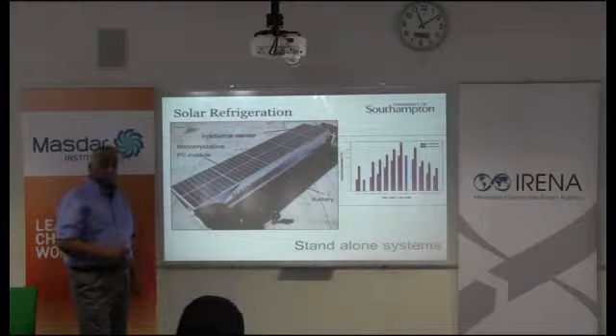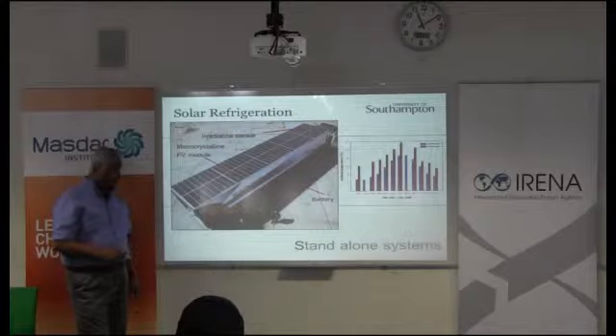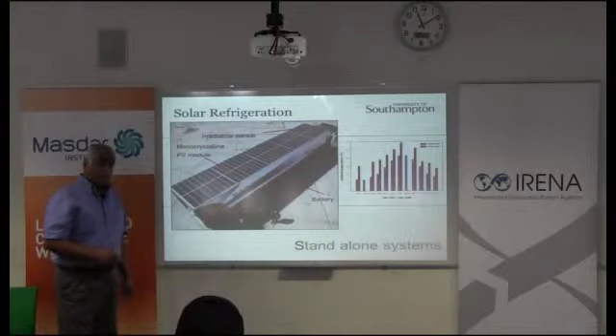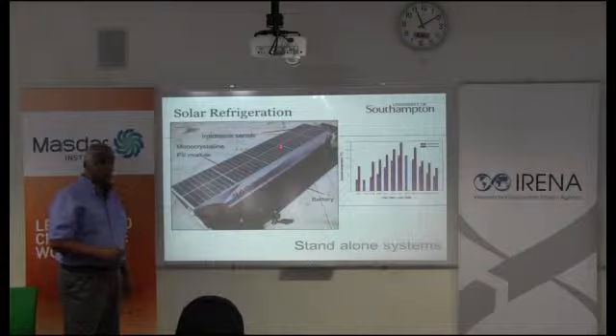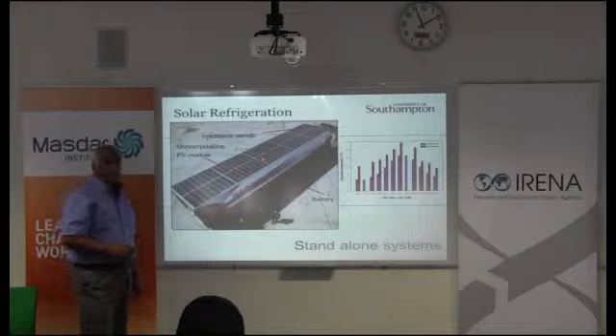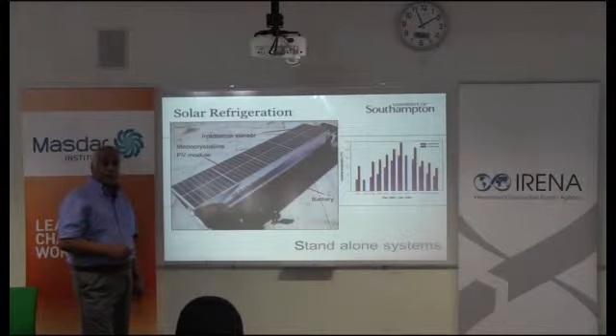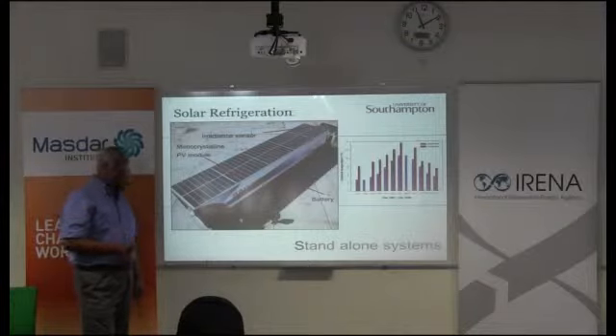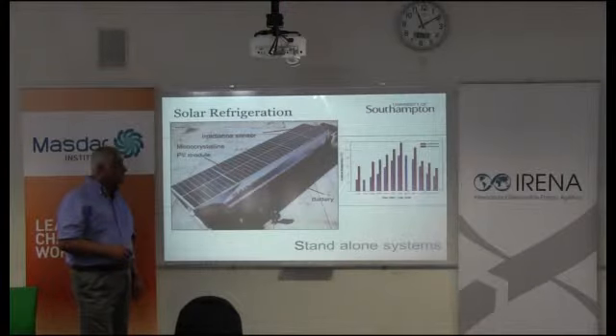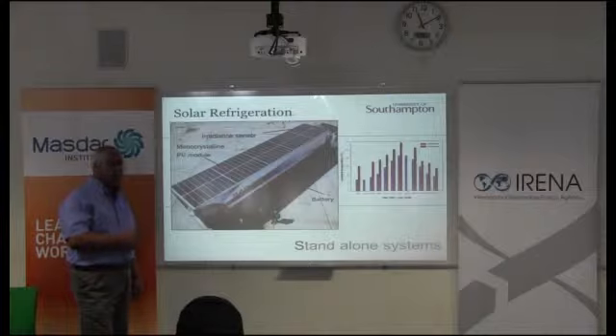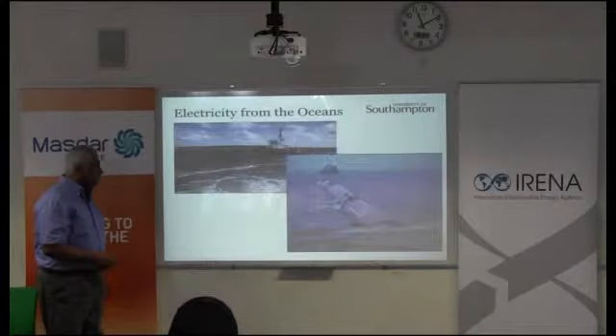This is 4.5 kilowatts, so it's just smaller modules. This is a 40-foot container, yes. But would it still work for a 20-foot container? It will work, because you've got less space to cool. But it depends on the ambient temperature you're working with, because here it goes to about 45-50 degrees and becomes very dirty. Once you open the door, you lose quite a lot of the cooling you have in there. I've got some nice graphs to show you, and there are some papers being published on this.